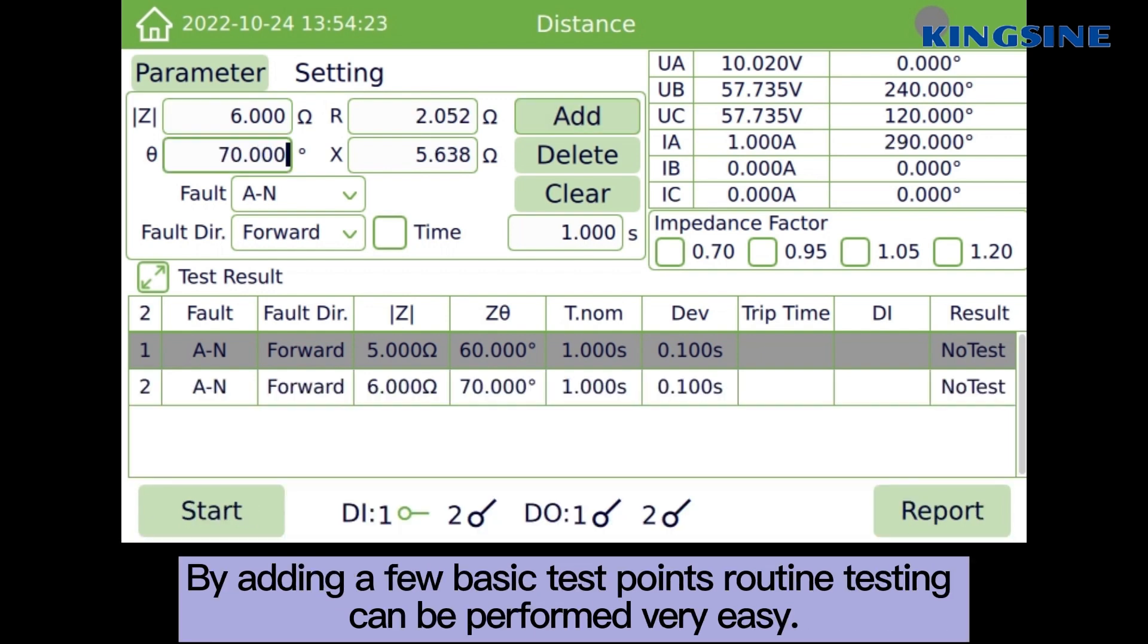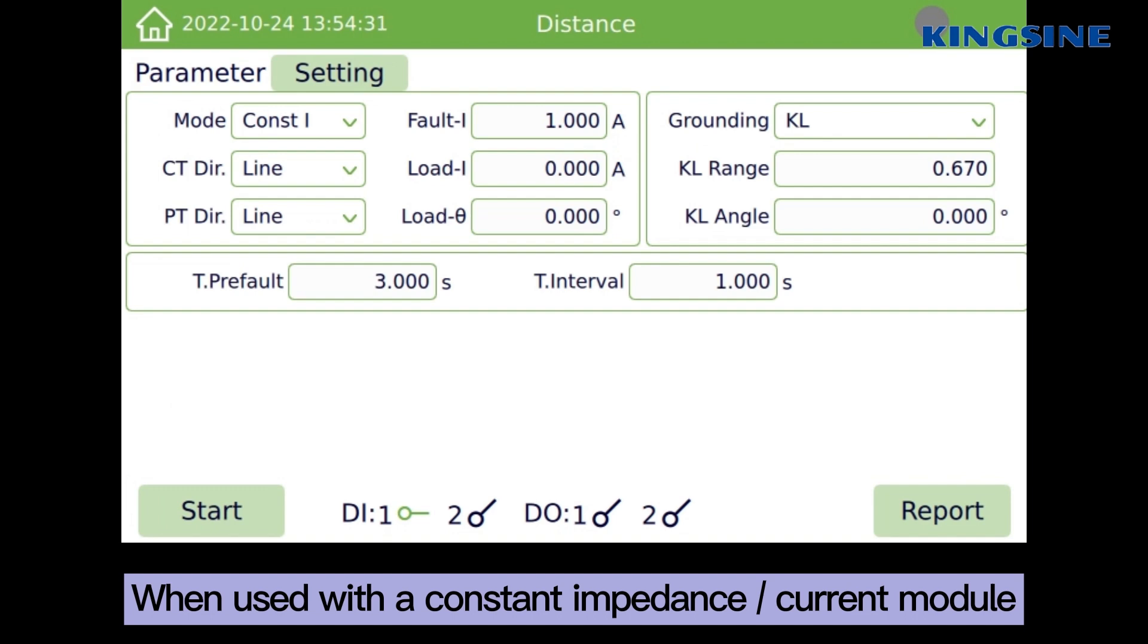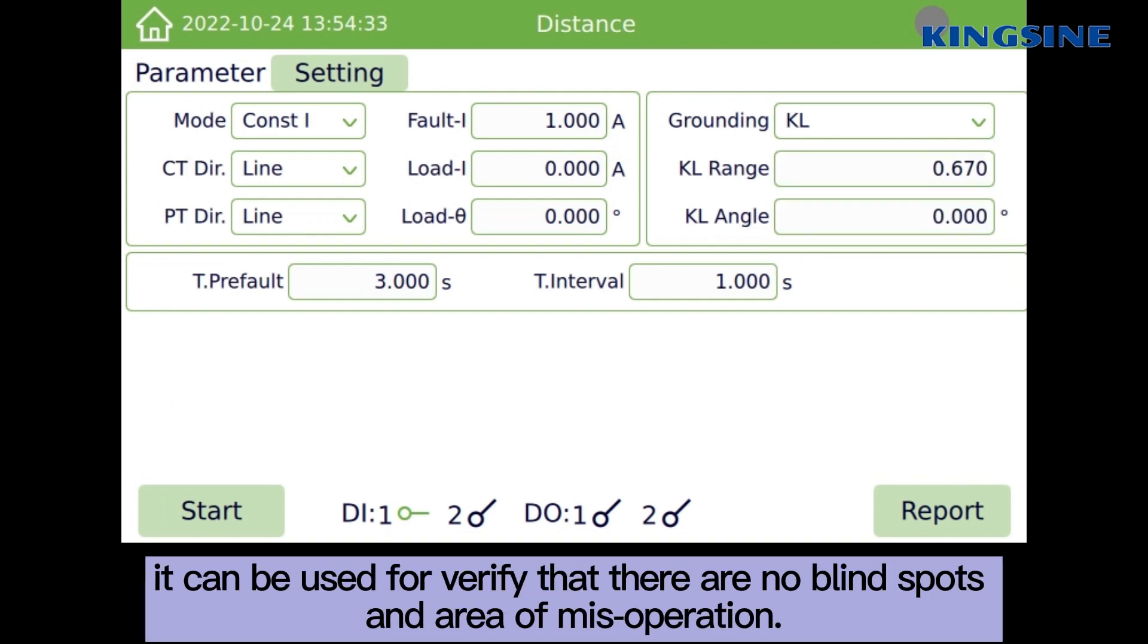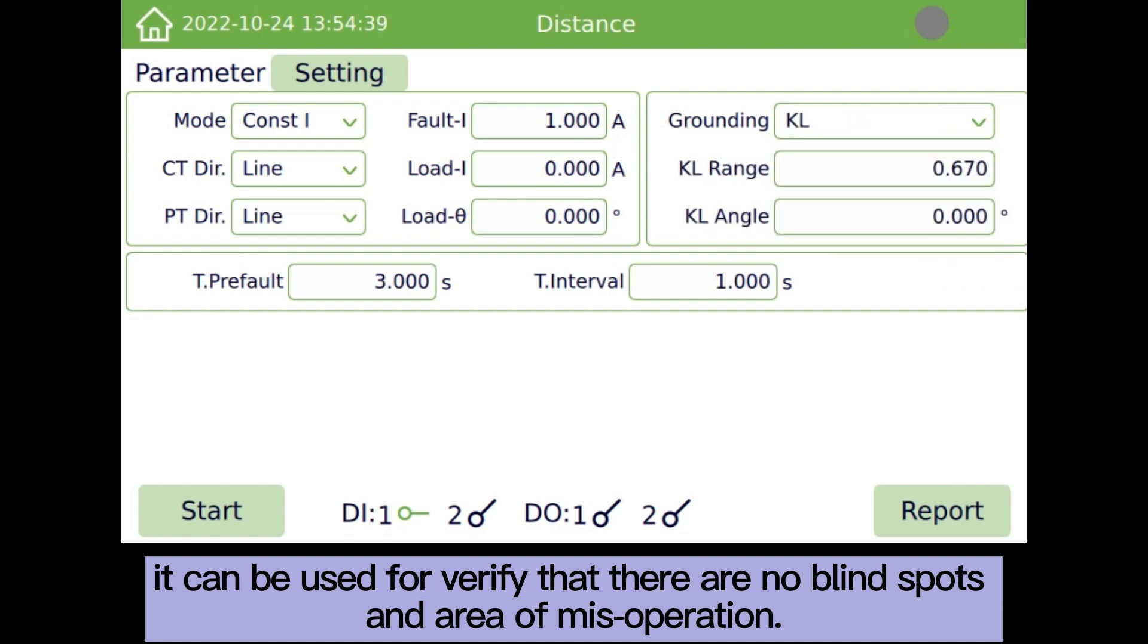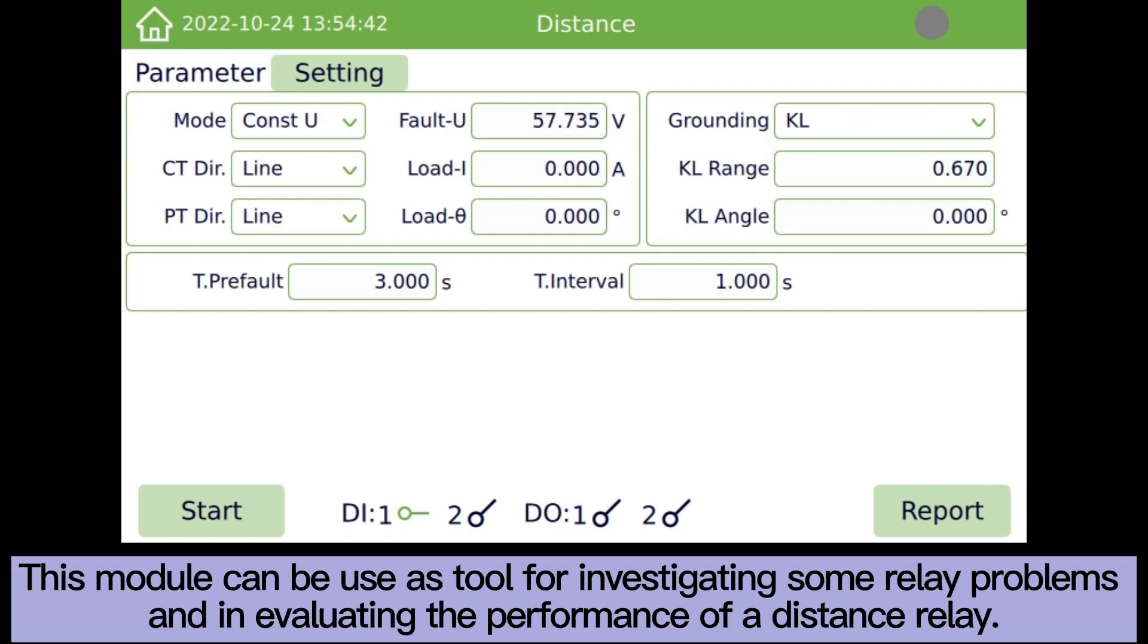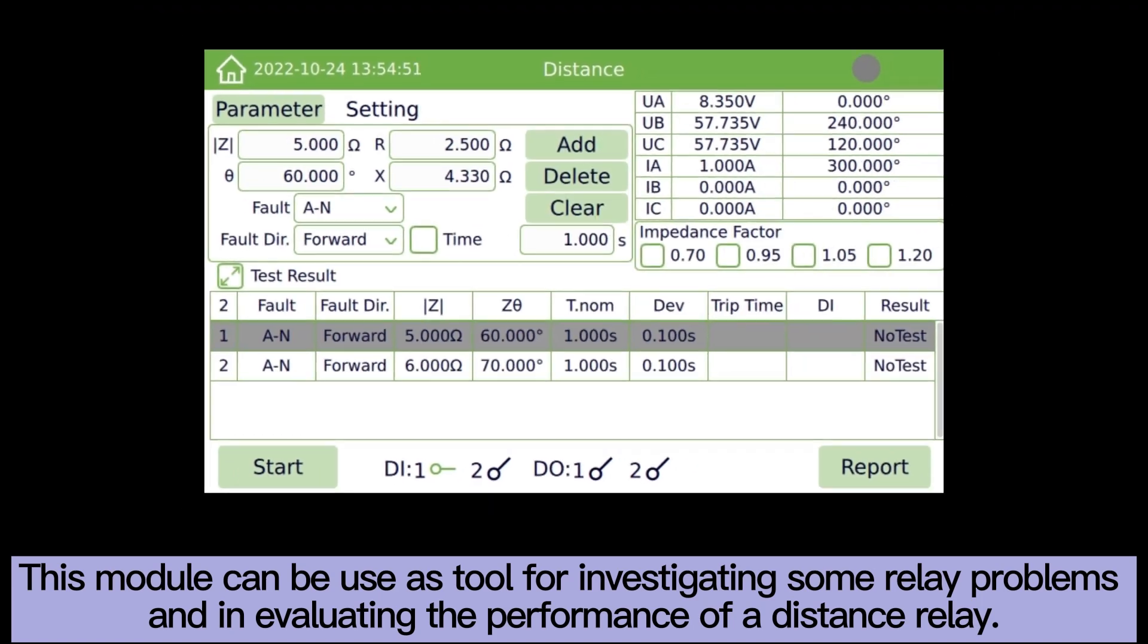By adding a few basic test points routine testing can be performed very easy. When used with the constant impedance current module, it can be used for verify that there are no blind spots, and area of misoperation. This module can be used as tool for investigating some relay problems, and in evaluating the performance of a distance relay.